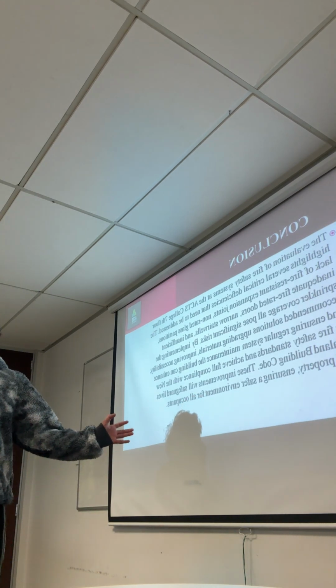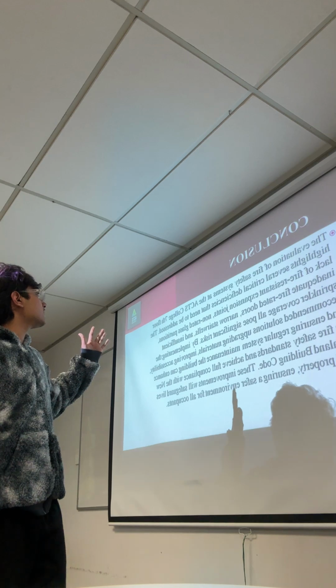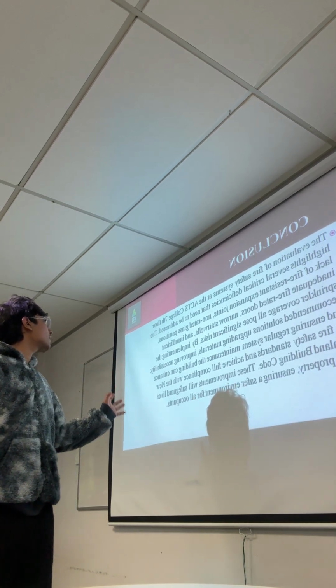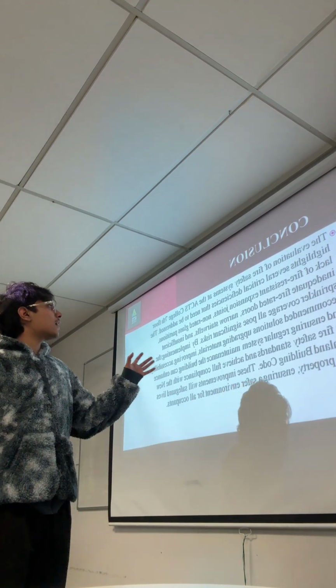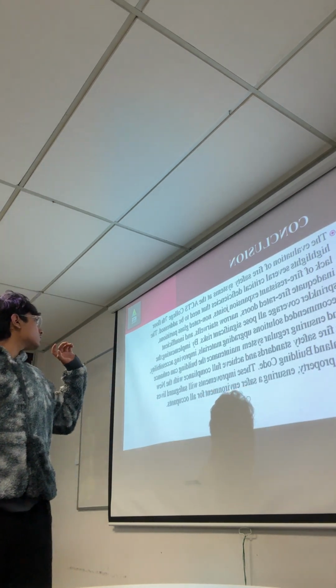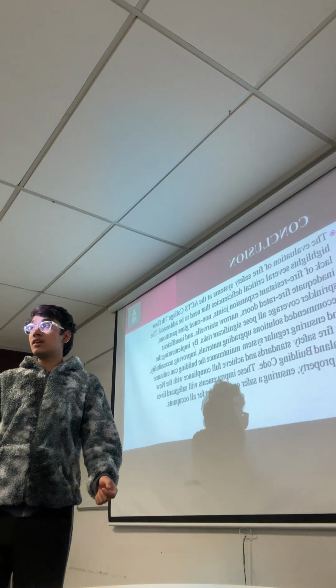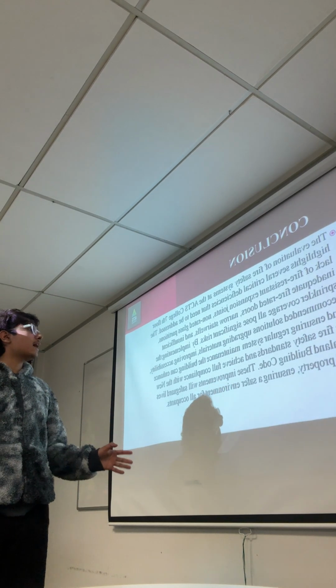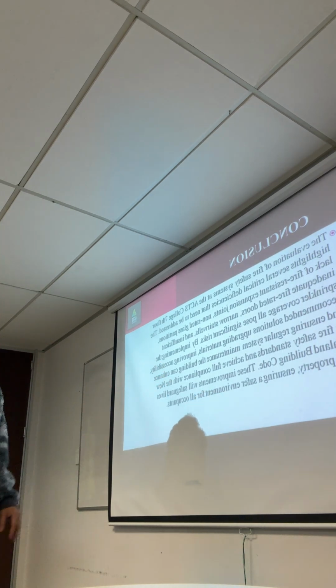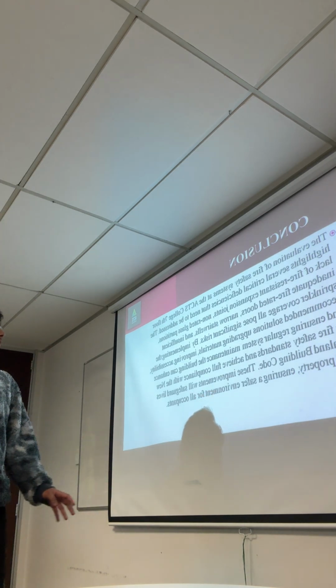So the evaluation of fire safety systems at ACTS College 7th floor highlights several critical deficiencies that need to be addressed. The lack of fire resistance expansion joints, non-rated glass partitions, inadequate fire rated doors, narrow stairwells, and insufficient sprinkler coverage all pose significant risks. By implementing the recommended solutions, upgrading materials, improving accessibility, and ensuring regular system maintenance, the building can enhance its fire safety standards and achieve full compliance with the New Zealand Building Code NZBC. These improvements will safeguard lives and property, ensuring a safer environment for all occupants inside the building.